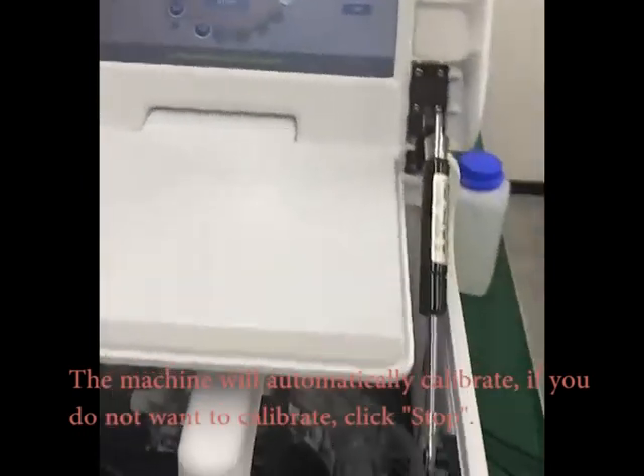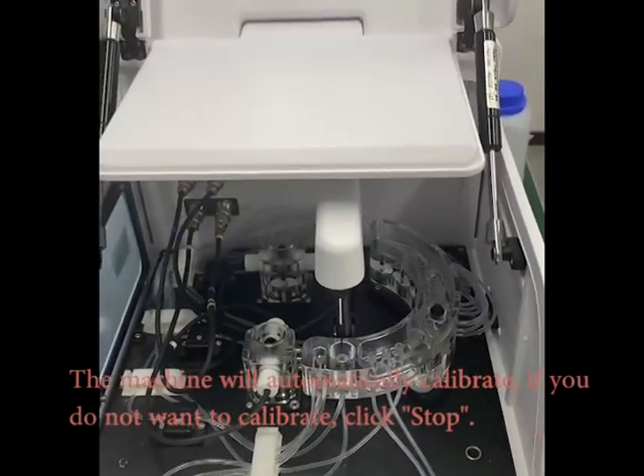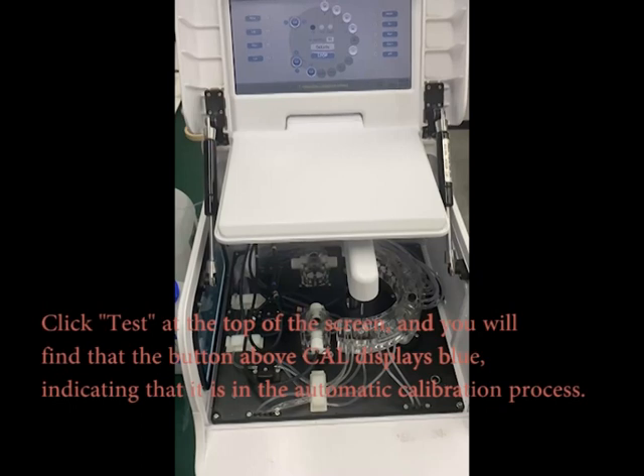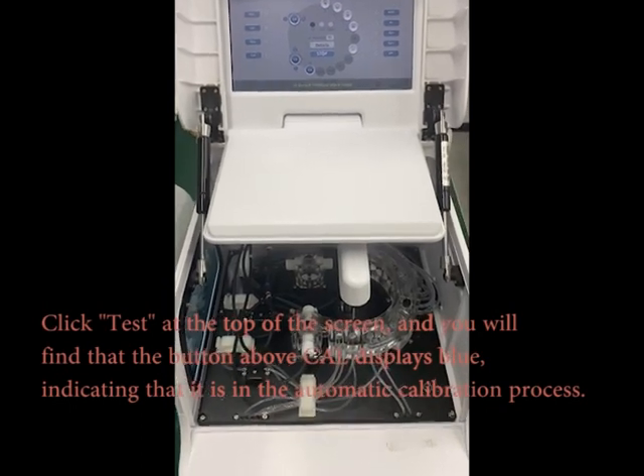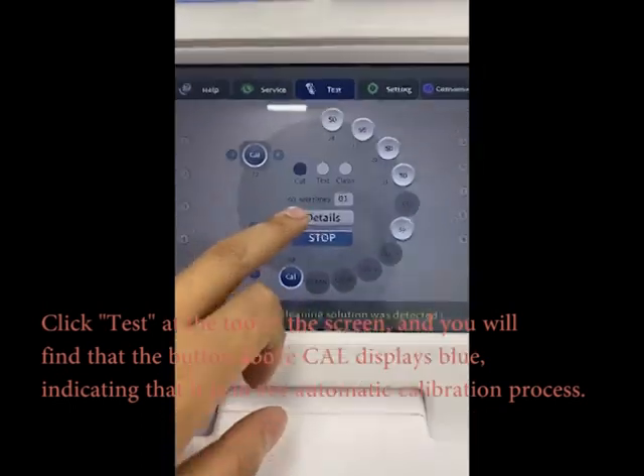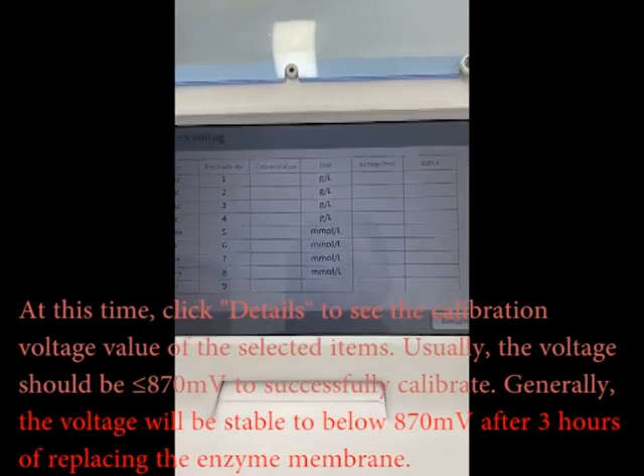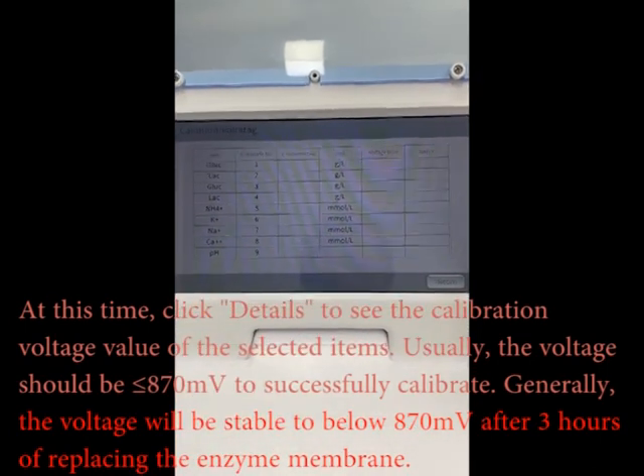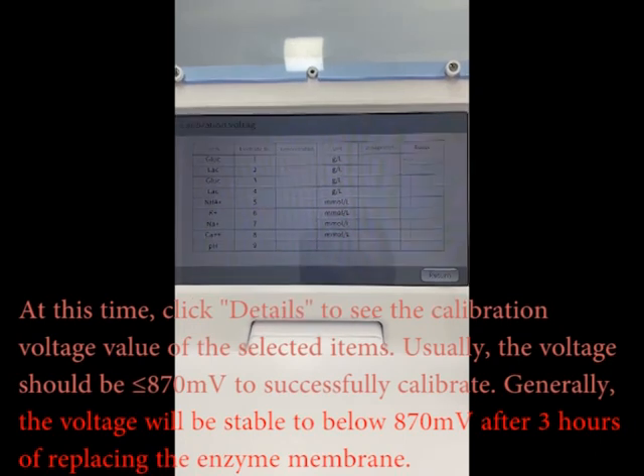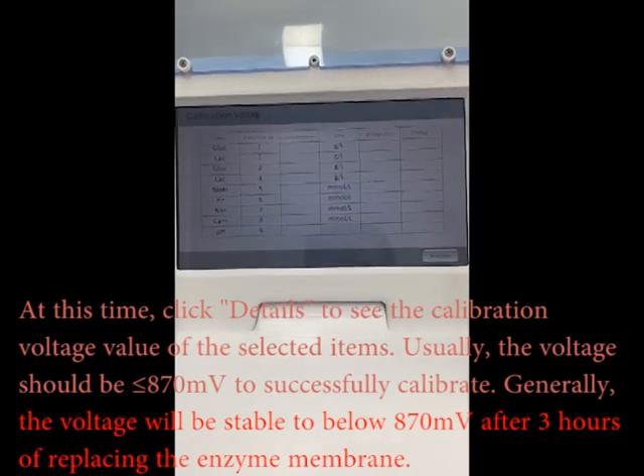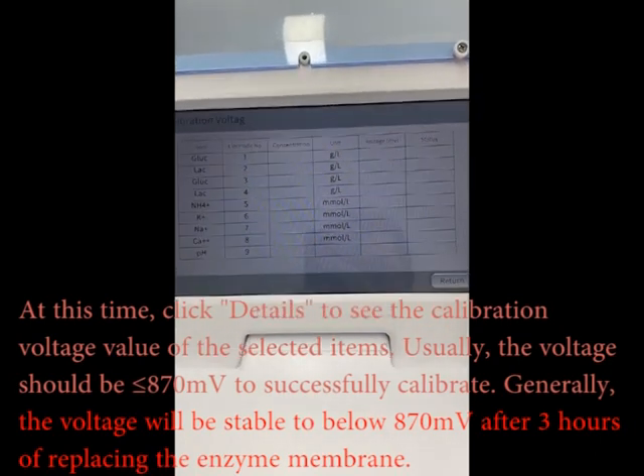The machine will automatically calibrate. If you do not want to calibrate, click Stop. Click Test at the top of the screen. At this time, click Details to see the calibration voltage value of the selected items. Usually, the voltage should be less than or equal to 870 mV to calibrate successfully.